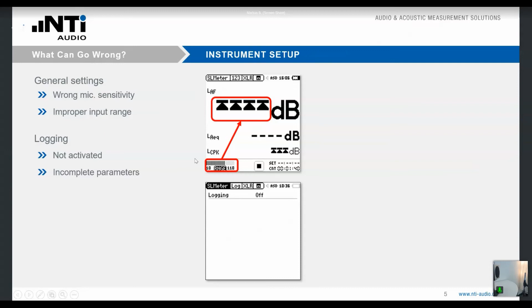Another possible problem is if you have selected the wrong input range. For instance, this can lead to an overload, which would be represented by these arrows here. So adjusting the input range to the expected sound level is a very important part. And further on, maybe you have forgotten to activate the logging, which will result in a complete loss of data when you have completed your measurement, because they're just not saved on the instrument. Maybe the measurement parameters have been activated incompletely, so there are some measurements missing, and you only notice that after returning to your office.